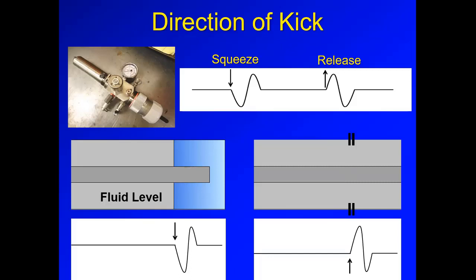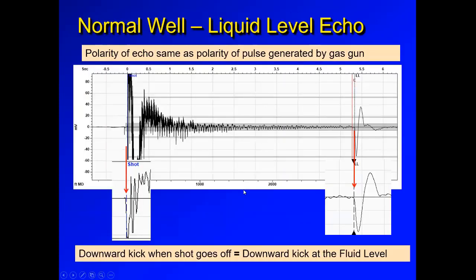So for us, it's really important to highlight that down kicks are reflected from a decrease in the cross-sectional area, and the opposite, up kicks, are coming from increases in cross-sectional area. We'll see some examples of that as well. This is a real example, real data, fluid level shot. We see small echoes along the trace, and those are actually tubing collar echoes.